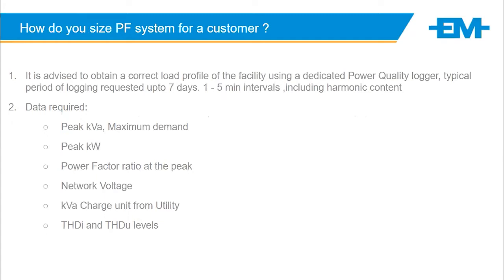So how would we size it for a customer? As I mentioned before, I would advise putting down a power quality logger. There's a couple of reasons for this, and we'll talk about it once we talk about harmonics. And for the logging interval, I would typically ask for around 7 days and 1 to 5 minute intervals on the data points. So what is the data? The peak kVA, the peak kilowatt, the power factor ratio, network voltage, the actual charge from the utility, and harmonic levels for voltage and current. The loggers we sell do all this. You can set them down to 1 second, and they will continuously trend on the memory cards for a period. Then once you've recorded, you can share the logging with me, and I can assist you on sizing these systems. Or as you get up to speed, or you may already be up to speed, you can size these systems by yourself. Okay, and then you're welcome to bounce it off me to see if we're all on track.